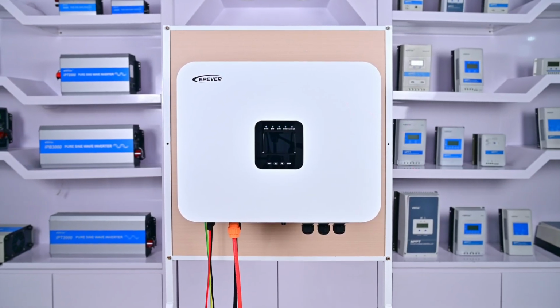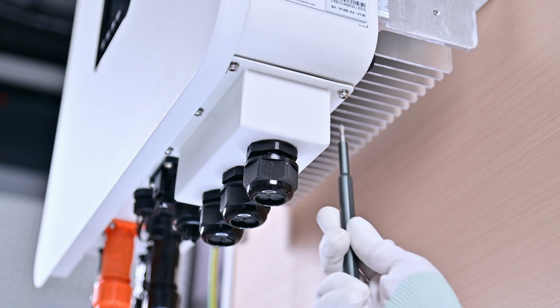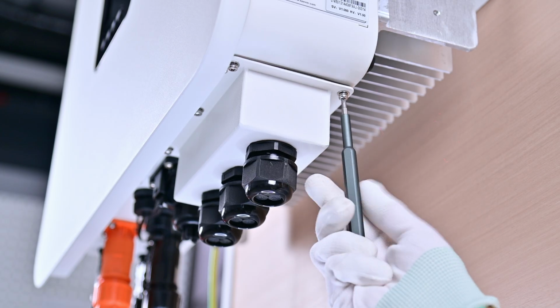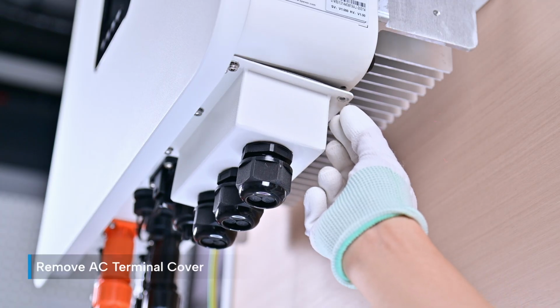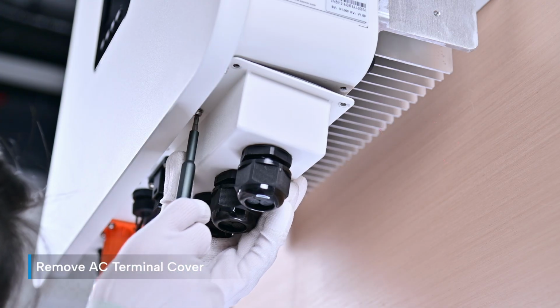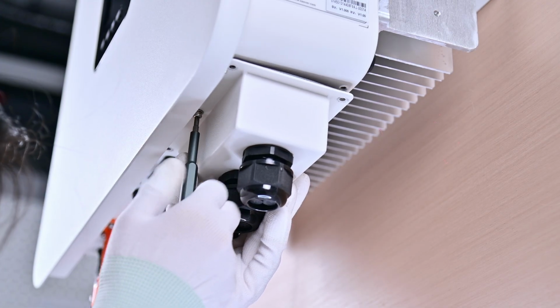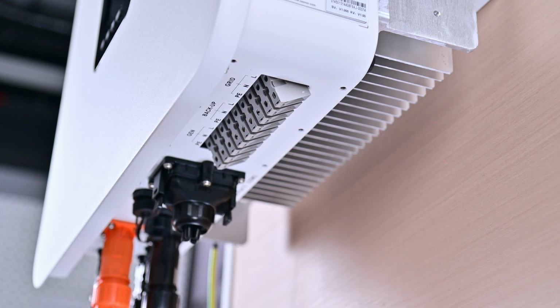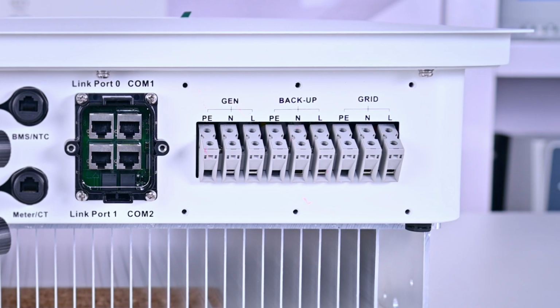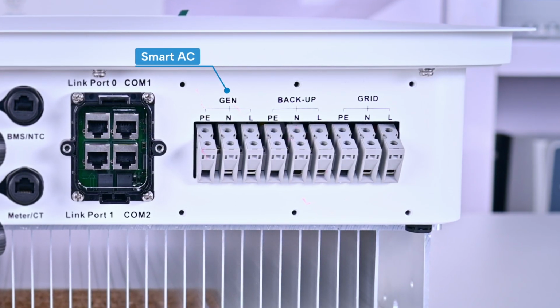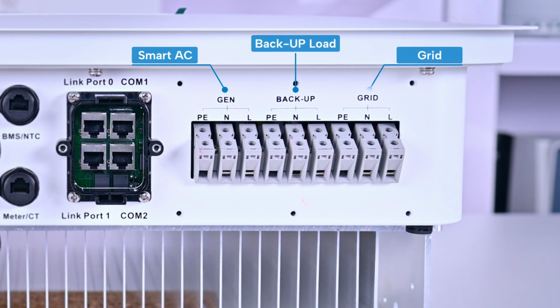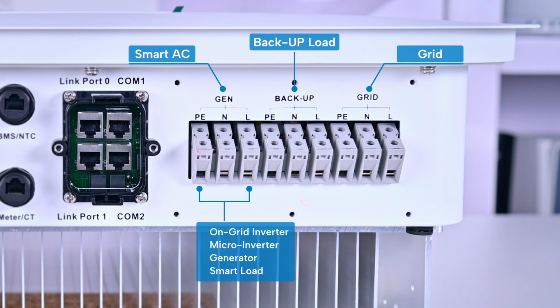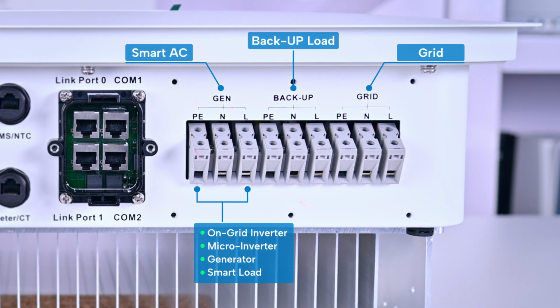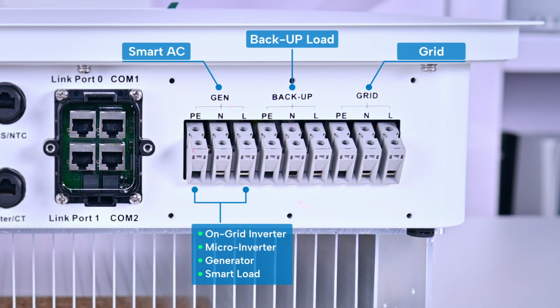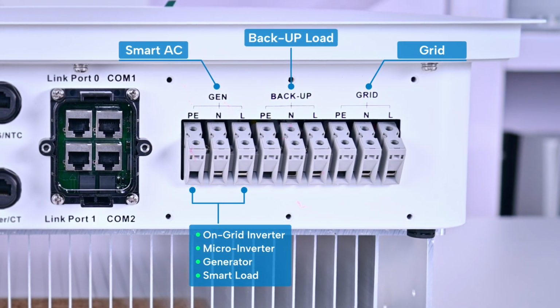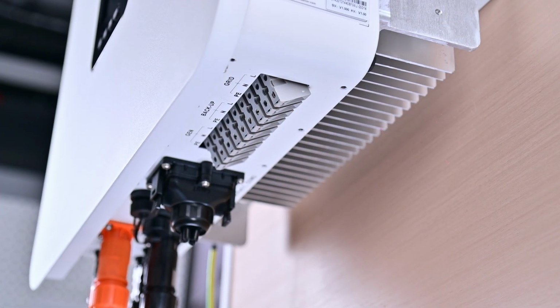Now we can connect the AC loads. First, remove the AC terminal cover. The AC terminals from left to right are Smart AC Connection Port, Emergency Load Connection Port, and the Grid Connection Port. The Smart AC Connection Port can be used to connect grid-tied inverters, microinverters, or generators. You can choose to connect any of the above devices based on your specific situation or leave the port empty. Here, we will leave it empty.